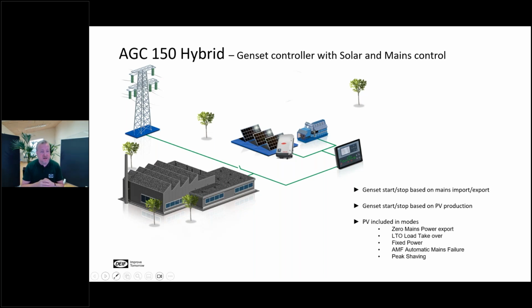All of this can be started either by how much we are importing from the mains, but we can also do it based on the PV production, because you could maybe squeeze the PV to a very high level, and then you want to start the genset to support that part. So all of this is automatic. And if some of you are coming from the genset world, you will know quite a few of these standard features like zero mains export, load takeover, fixed power, and so on, automatic mains failure. In many rural areas the grid is not stable, so we can take over the load as we see that the mains are failing, or we know that the mains will be disconnected. All of this is inside one controller.